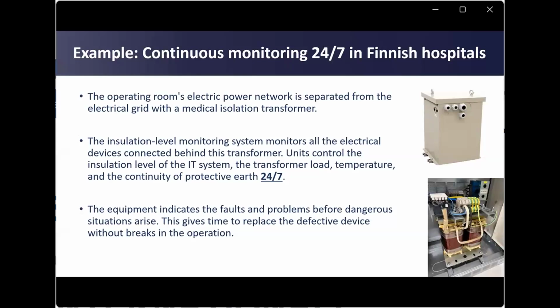This is how the system works in Finland and Europe. The electric power network of the operating room is separated from the electrical grid with a medical isolation transformer. The insulation level monitoring system monitors all the electrical devices connected behind this transformer. Units control the insulation level of the IT system, transformer load, and the temperature, as well as the continuity of the protective earth 24/7. The equipment indicates the faults and problems before dangerous situations arise. This gives time to replace the defective device without breaks in the operation.